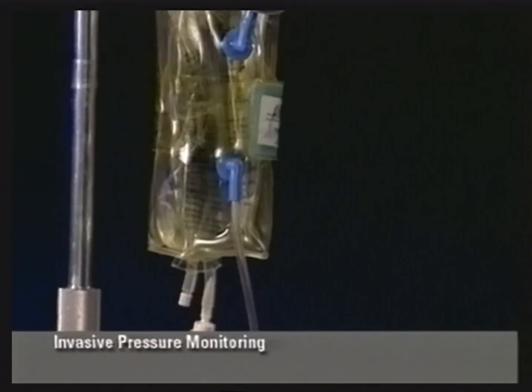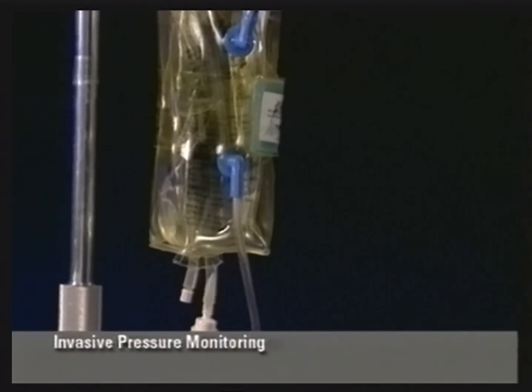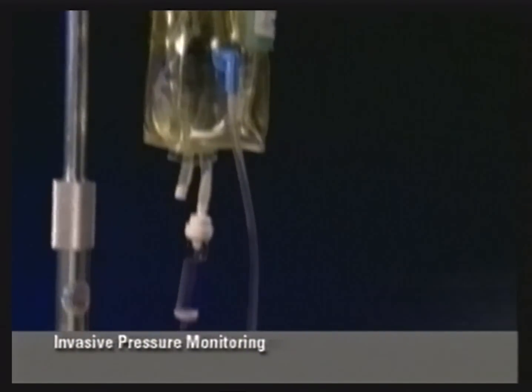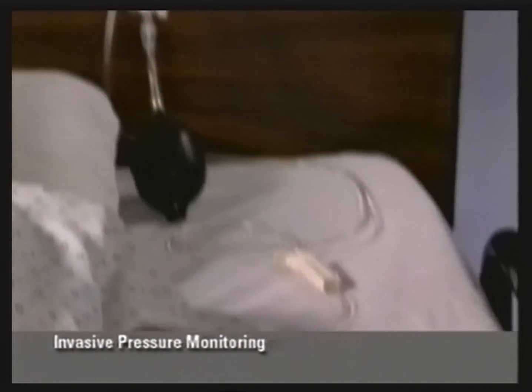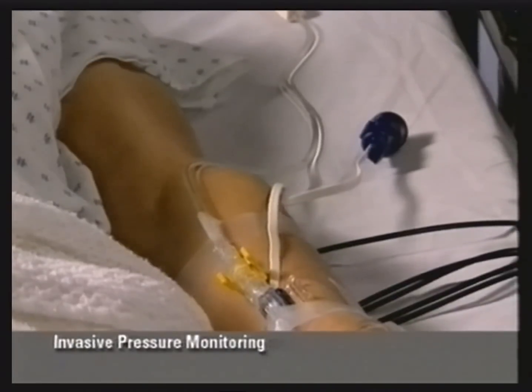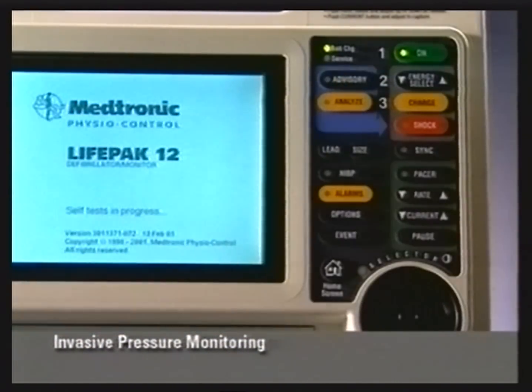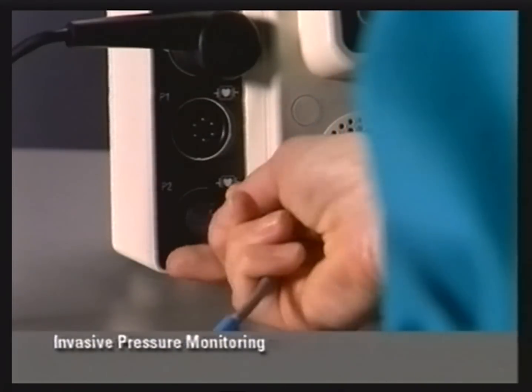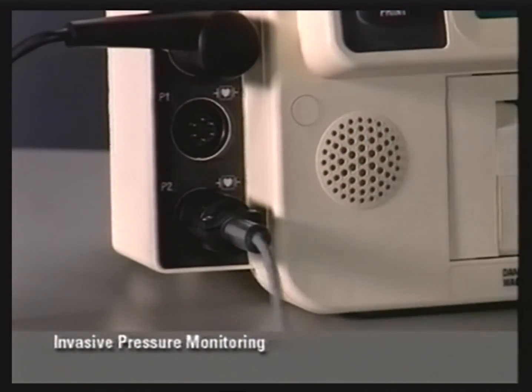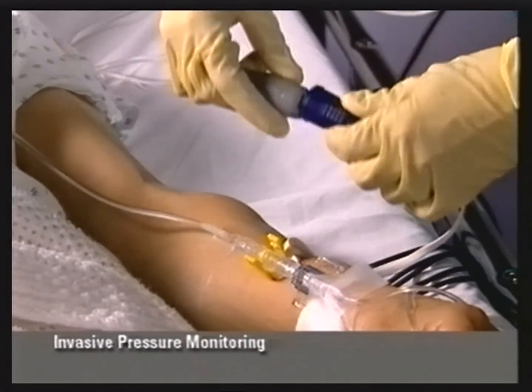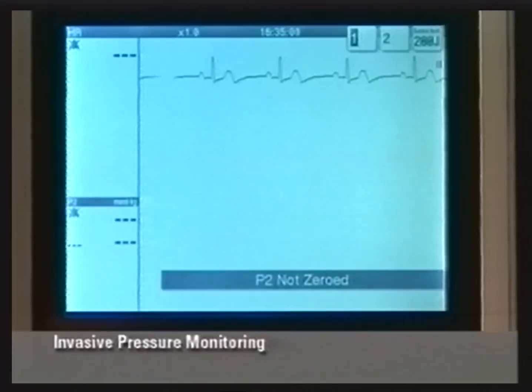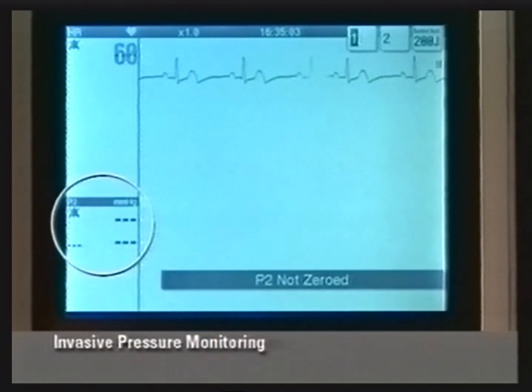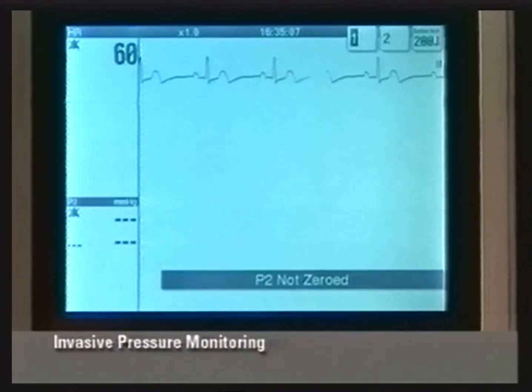To perform invasive pressure monitoring with the Lifepak 12 monitor, first prepare the transducer and flush system according to the instructions provided with the transducer and flush system, or according to your local protocol. Turn on the monitor and connect the invasive pressure cable to one of the invasive pressure connectors on the monitor and to the transducer. The pressure parameter area appears on the monitor screen. Use the default label P2 or change the label to match the pressure to be monitored.